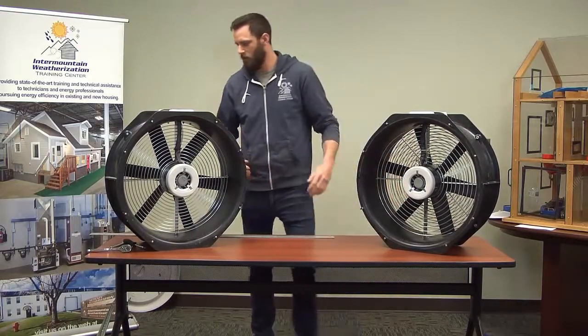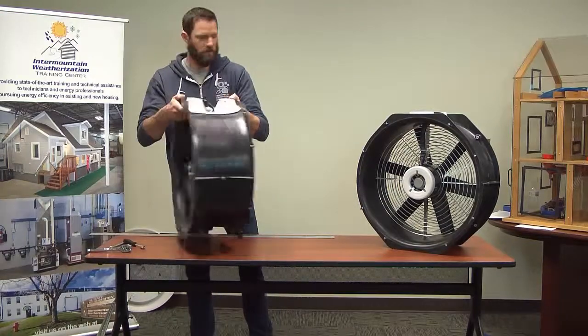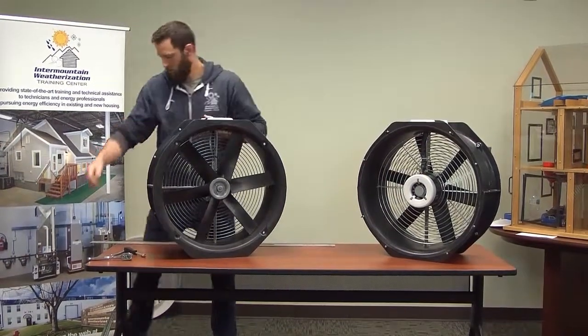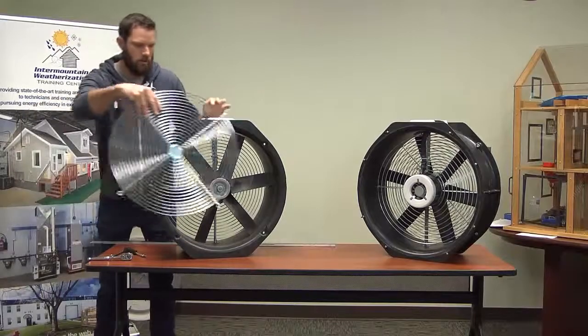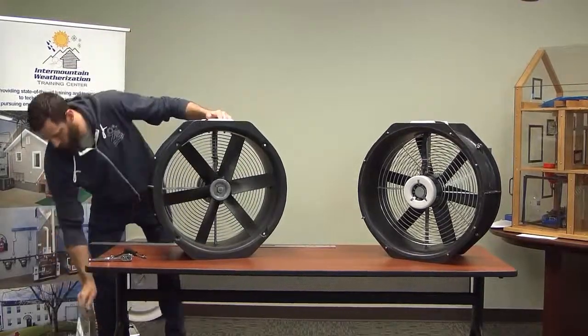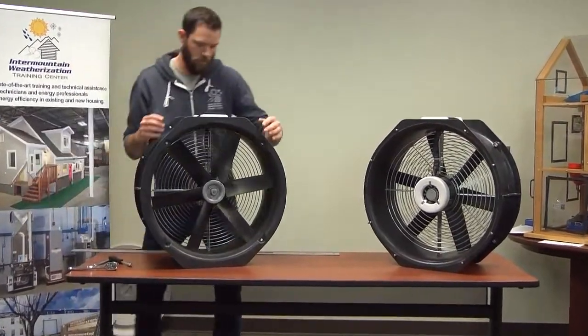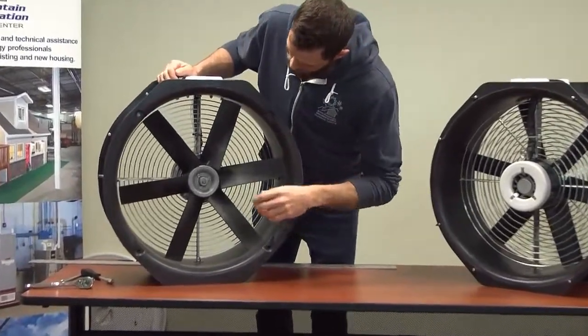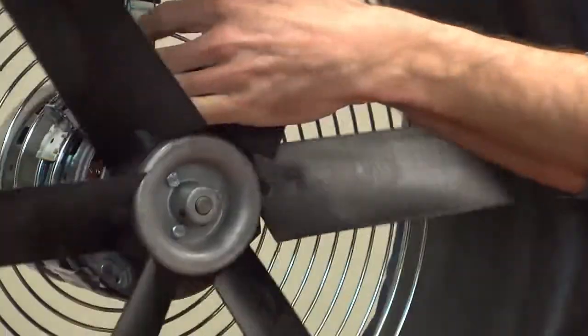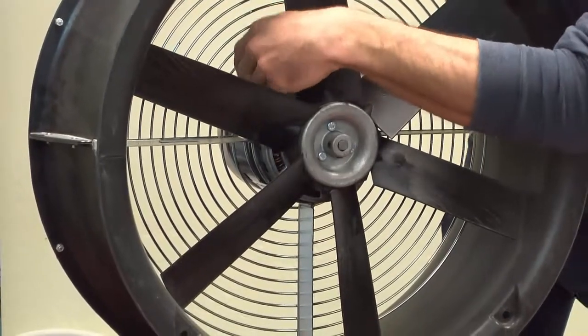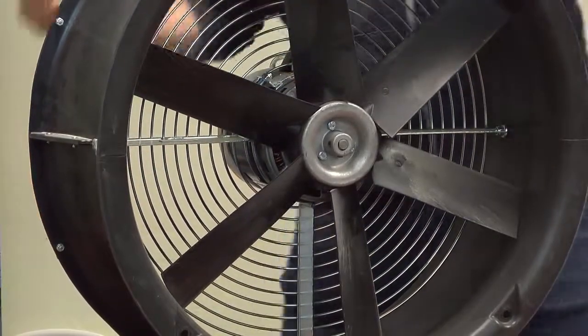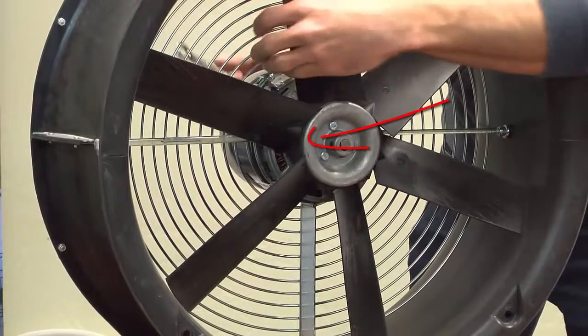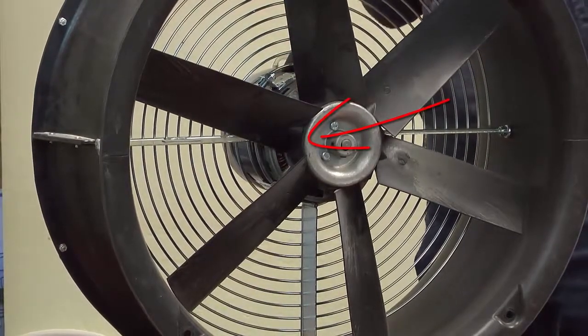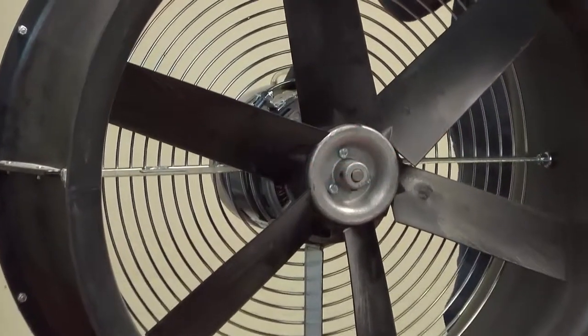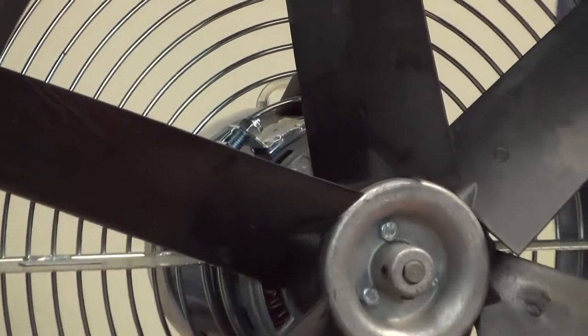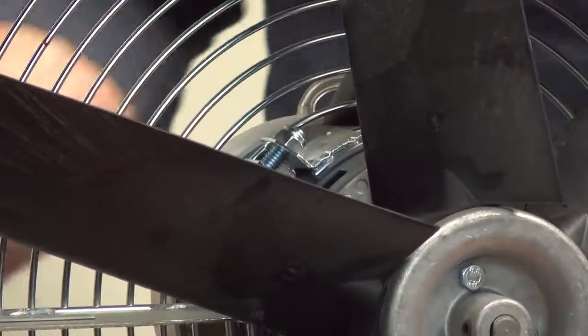at the right depth. And what that will look like is if you take this cage off the back side of your blower door, or your blower, you can get to the motor mount right here on the inside and loosen that up, and that'll allow you to adjust that fan flow sensor either in or out a little bit for what you need.